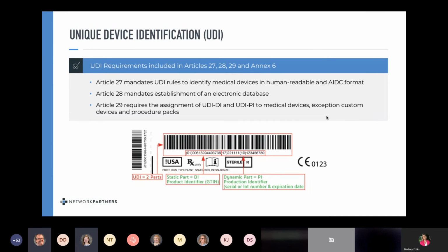Great. Next question. GS1 guidance suggests that BUDI does not go on packaging. Are you familiar with their guidance? I think there are still a few questions with the BUDI as EUDAMED comes up and those requirements get squared away. It'll become clearer. We are suggesting to our clients to hold off on making any BUDI decisions at this time. To Lindsay's point earlier, you should be aware of what they are and what implications they could cause if they go ahead as currently configured.